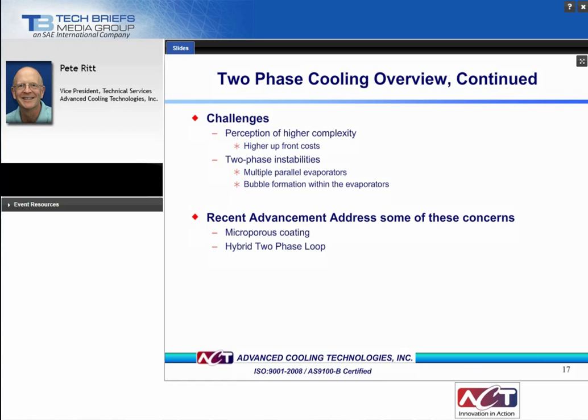If two-phase flow is so superior, then why hasn't it been accepted by the market? Historically, two-phase systems are considered more complex than pumped liquid systems, requiring more upfront development costs. One clear challenge with this technology is the potential flow instabilities associated with two-phase flow. At the system level, having multiple parallel evaporators can cause flow instability issues if the applied heat flux and pressure drops are improperly balanced. Within the evaporators, bubble formation at nucleation sites can be erratic, and these bubbles can create unintended back pressures, which can restrict flow and result in instability and thermal uniformity issues. This is especially evident in microchannel coolers, which have multiple channels in parallel.